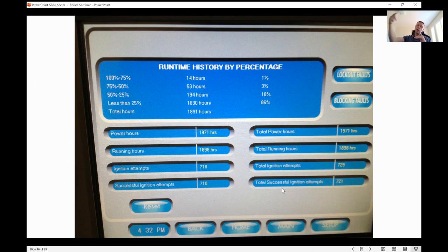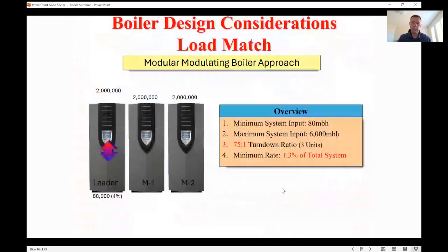Overshoot it, shut off on supply set point, but the room's still cold, still calling. Let that cool down a bit. On, off, right? You're going to be less efficient and you're going to basically need maintenance faster. I don't care what that piece of literature says, the actual efficiency of the boiler is... it could be 3 points higher in efficiency. This one here will have a better overall boiler plant efficiency.